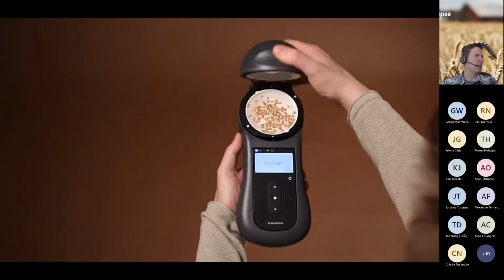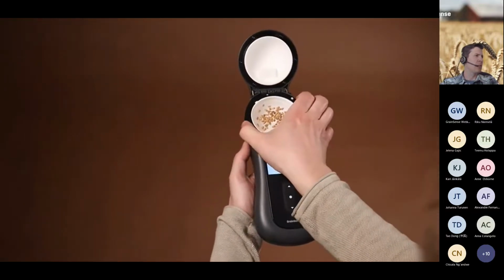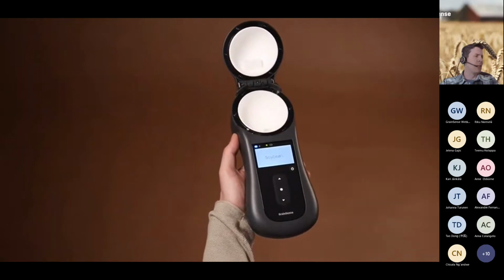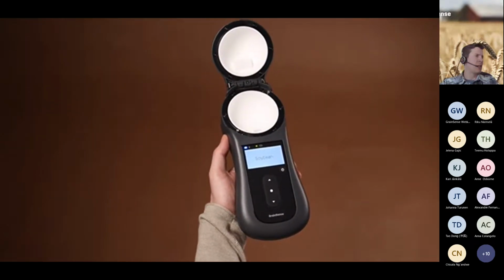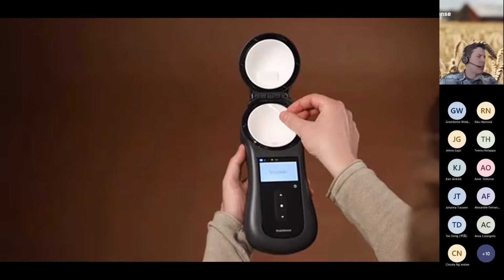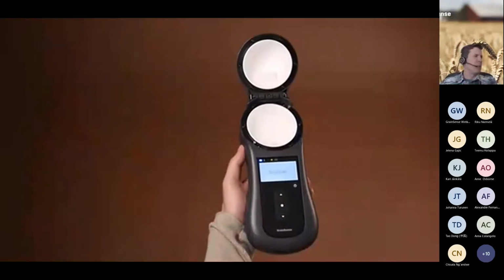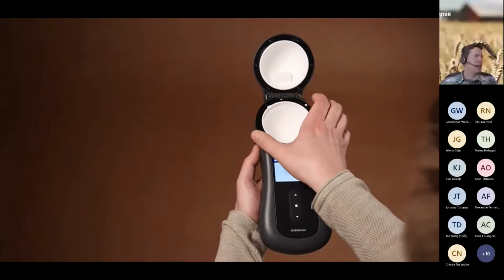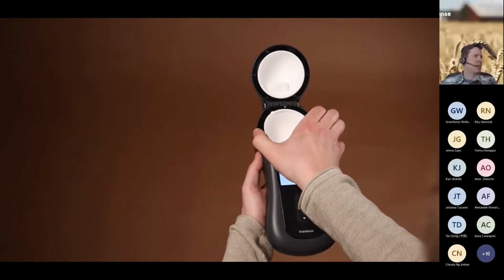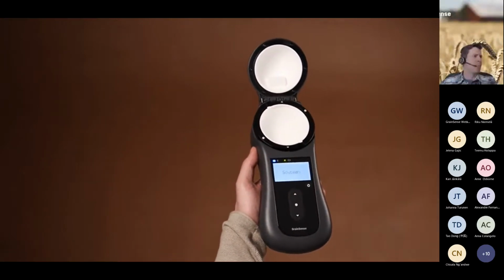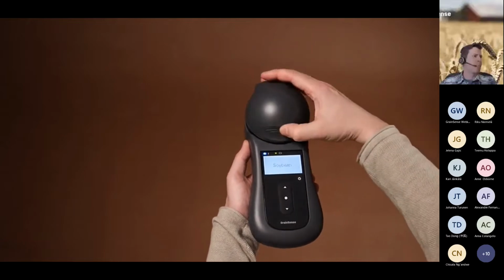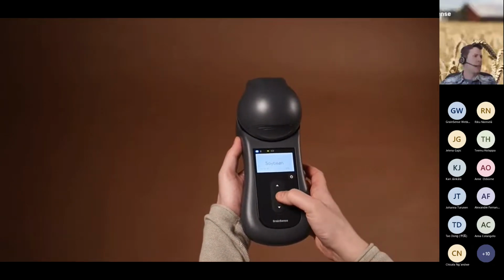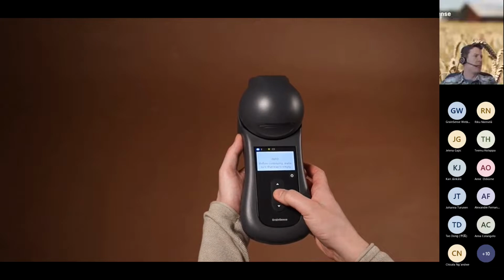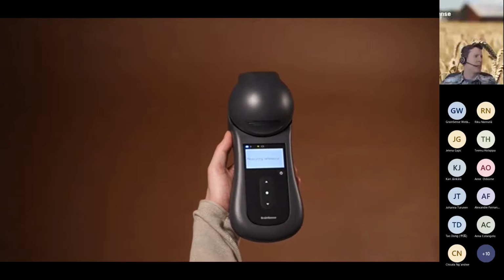So first we'll take the glass tray out, and for the glassless tray, which we need for soybeans, first you put on the Teflon sheet, and then you put the ring to secure the sheet in place. So this is considered the glassless tray. Again, with the glassless tray, you need to make sure you run a reference measurement when the tray is empty.